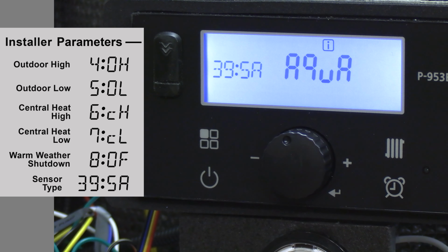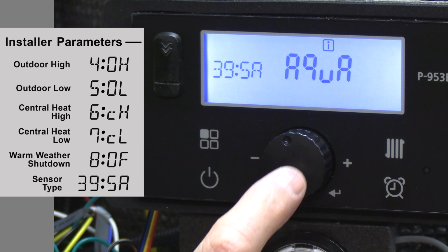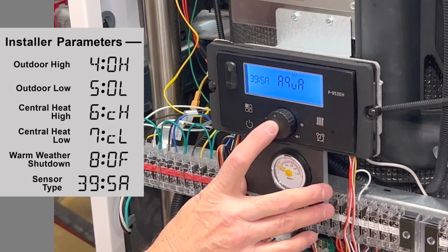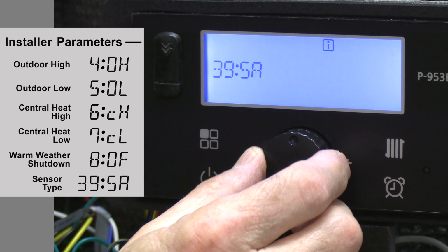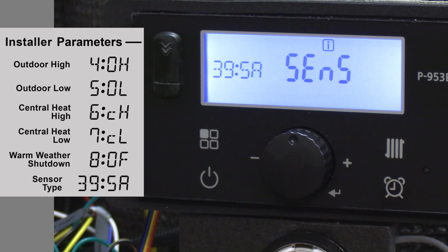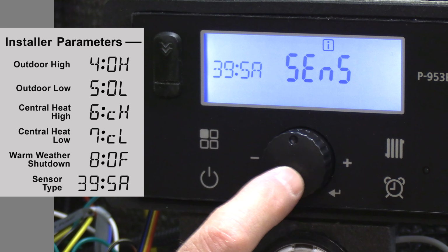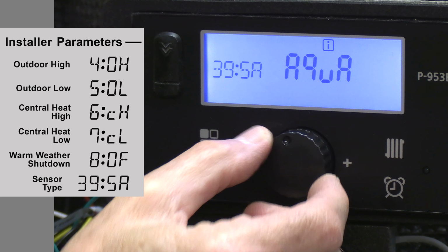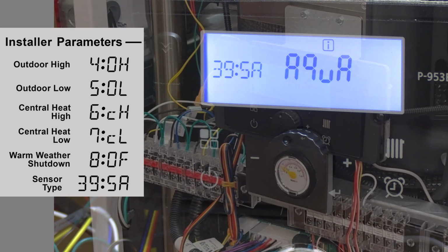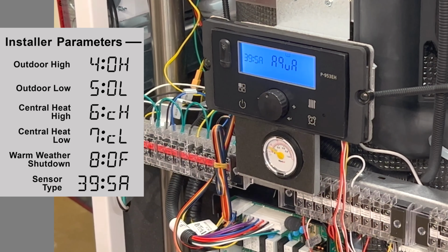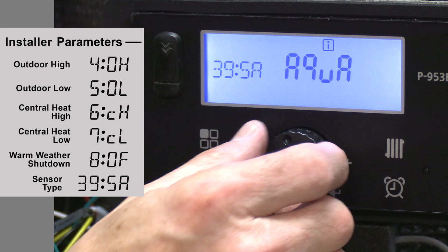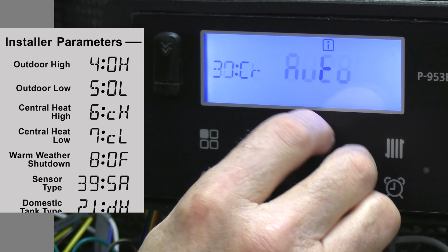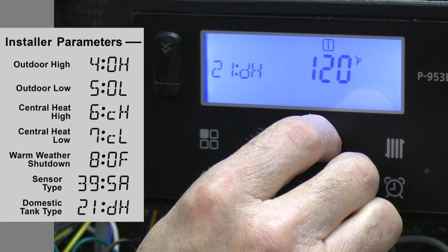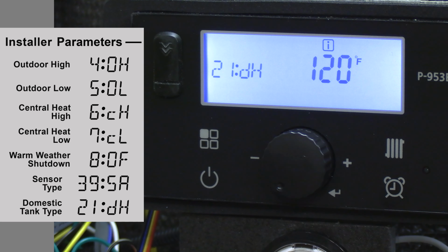So is that a mechanical aquastat, or are you using a sensor? If you are using a sensor, press the scroll select button until it flashes, and then you can choose sensor, okay? And then you would store that again. In our example, we are using an aquastat, so I'm going to come back and choose aquastat. Next, we need to go back to parameter 21. So I'm going to scroll back to parameter 21, and this is my domestic storage tank temperature, okay? And the range is from 95 degrees to 180.